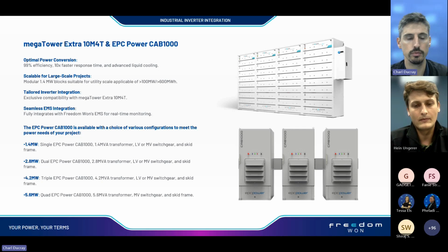Yeah, absolutely. Each independent inverter installation is coupled with an isolation transformer, and you can parallel up to 4 inverters on one isolation transformer, operated in parallel. But if you have independent systems, there is in theory no limit to how many you can parallel, provided there are isolation transformers and the engineering is done correctly, which has some complexity around it. As I said before, the biggest reference site I know of is around 200 megawatts, which shows it is possible. Whether that infrastructure is now needed in South Africa is a different question.